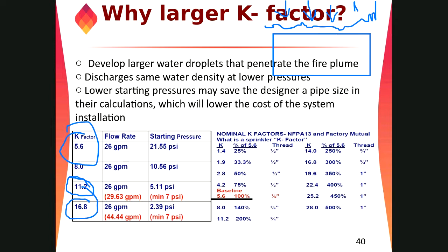Some sprinklers in high challenge fires provide 125 GPM, also 100 GPM, right? That is a huge quantity compared to an office installation where we need at least 15 GPM or 20 GPM, almost 5 times less. So these things need to be considered while you are designing for high challenge fires. Let's say if you are designing an extra hazard fire or group A plastics fire.